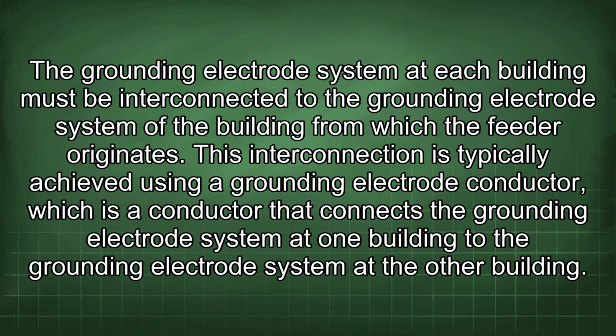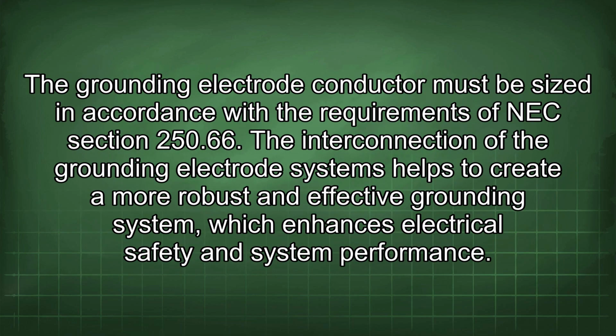The grounding electrode system at each building must be interconnected to the grounding electrode system of the building from which the feeder originates. This interconnection is typically achieved using a grounding electrode conductor, which is a conductor that connects the grounding electrode system at one building to the grounding electrode system at the other building. The grounding electrode conductor must be sized in accordance with the requirements of NEC section 250.66. The interconnection of the grounding electrode systems helps to create a more robust and effective grounding system, which enhances electrical safety and system performance.